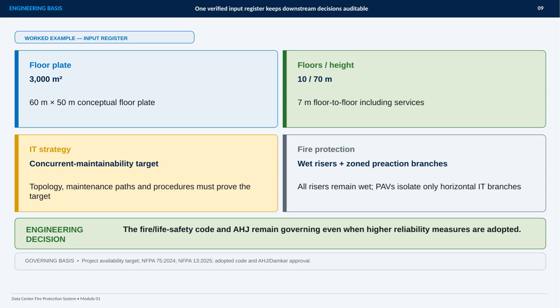The IT strategy targets concurrent maintainability, so the topology, maintenance paths, and operating procedures must demonstrate that the target can actually be achieved. For fire protection, the basis is wet risers combined with zone preaction branches. All risers remain wet, while preaction valves isolate only the horizontal IT branches. That distinction is important because it preserves the intended system behavior while supporting maintainability.